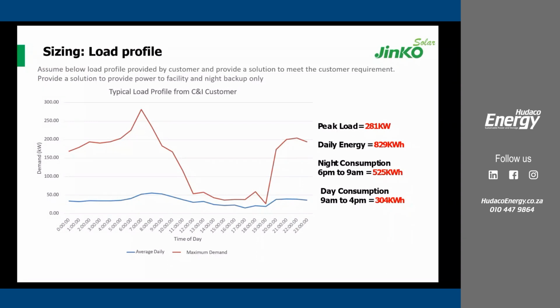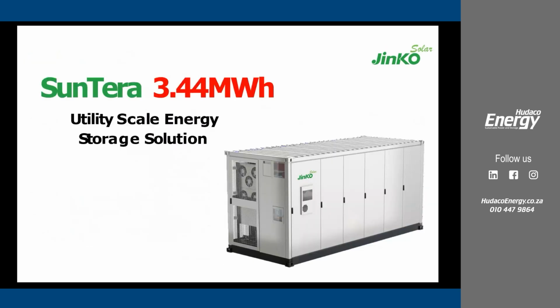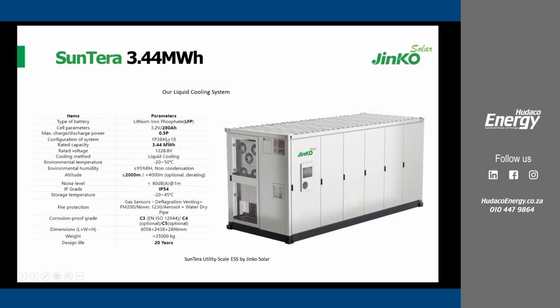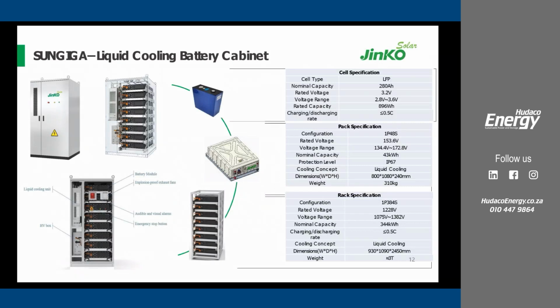So like I said, the SunTera 3.44 megawatt hours is actually made up of 10 racks of 344 kilowatt hours. Let me explain. This is one 3.44, basically 344 kilowatt hours. If you want 2 megawatt hours, you can have 8 units of this, so 8 by 344 kilowatt hours. That's not SunTera but SunGiga, the C&I version, which is liquid cooled. So 344 kilowatt hours, then you can have maybe 8 units in parallel to get that capacity, so 3.44 by 8.